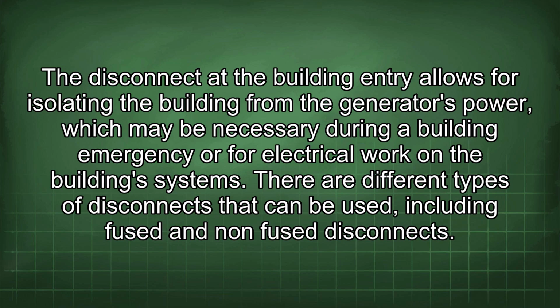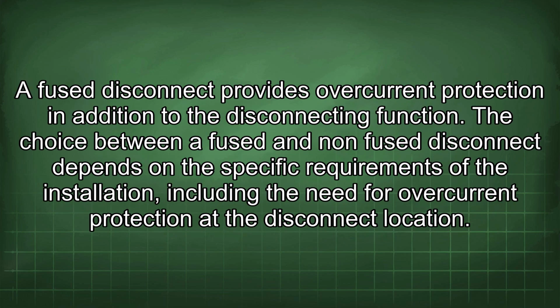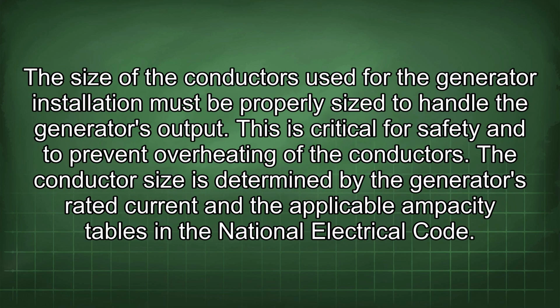There are different types of disconnects that can be used, including fused and non-fused disconnects. A fused disconnect provides overcurrent protection in addition to the disconnecting function. The choice between a fused and non-fused disconnect depends on the specific requirements of the installation, including the need for overcurrent protection at the disconnect location. The size of the conductors used for the generator installation must be properly sized to handle the generator's output. This is critical for safety and to prevent overheating of the conductors. The conductor size is determined by the generator's rated current and the applicable ampacity tables in the National Electrical Code.